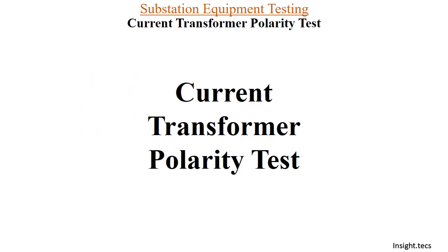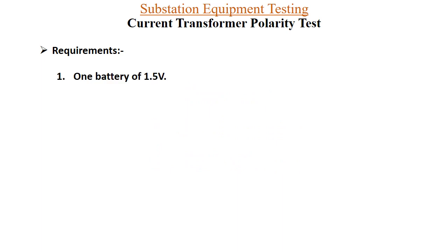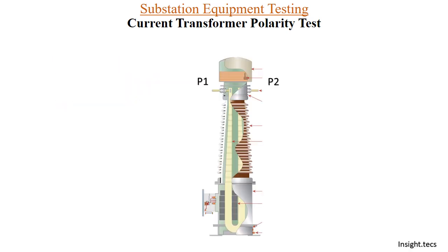Let's learn about CT polarity test today. First, let us see what basic things will be required to perform the polarity test. The first one is a 1.5 volt battery cell, which will be easily available to you, and a few extension wires.